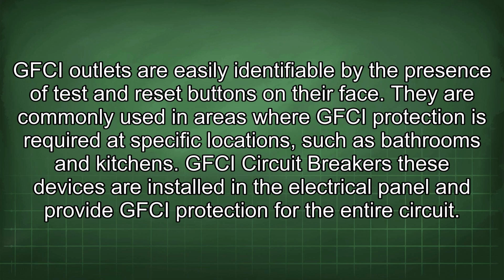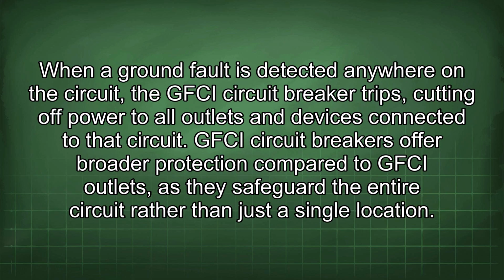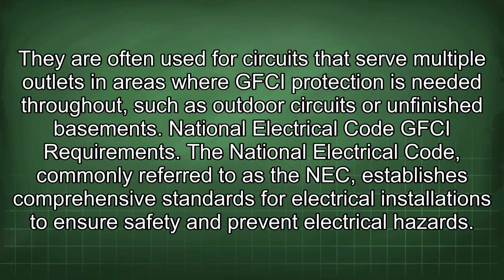GFCI circuit breakers: these devices are installed in the electrical panel and provide GFCI protection for the entire circuit. When a ground fault is detected anywhere on the circuit, the GFCI circuit breaker trips, cutting off power to all outlets and devices connected to that circuit. GFCI circuit breakers offer broader protection compared to GFCI outlets, as they safeguard the entire circuit rather than just a single location. They are often used for circuits that serve multiple outlets in areas where GFCI protection is needed throughout, such as outdoor circuits or unfinished basements.